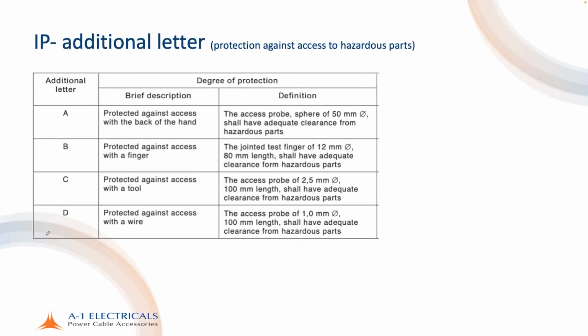My screen is visible, right? Yeah. The additional letter comes into the picture when your protection against access to hazardous parts is of a greater degree than your protection against ingress of solid foreign bodies, or there is no declared protection against ingress of solid foreign bodies, but there is protection against access to hazardous parts. So only protection for humans accessing hazardous parts, but not against dust going inside the equipment. So protection from humans accessing the hazardous parts is more than the protection against dust going inside.